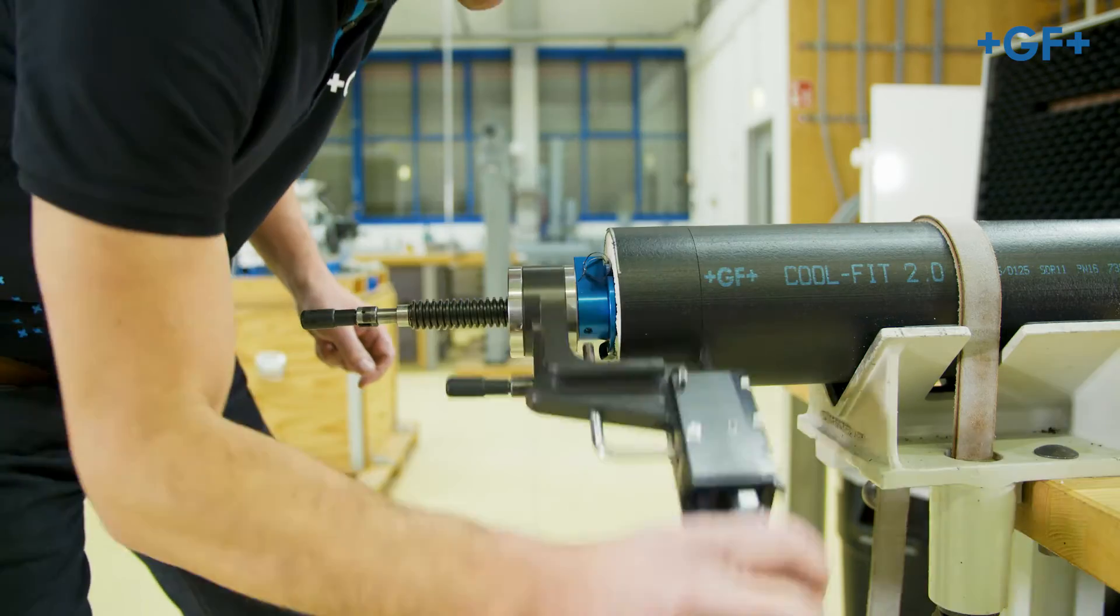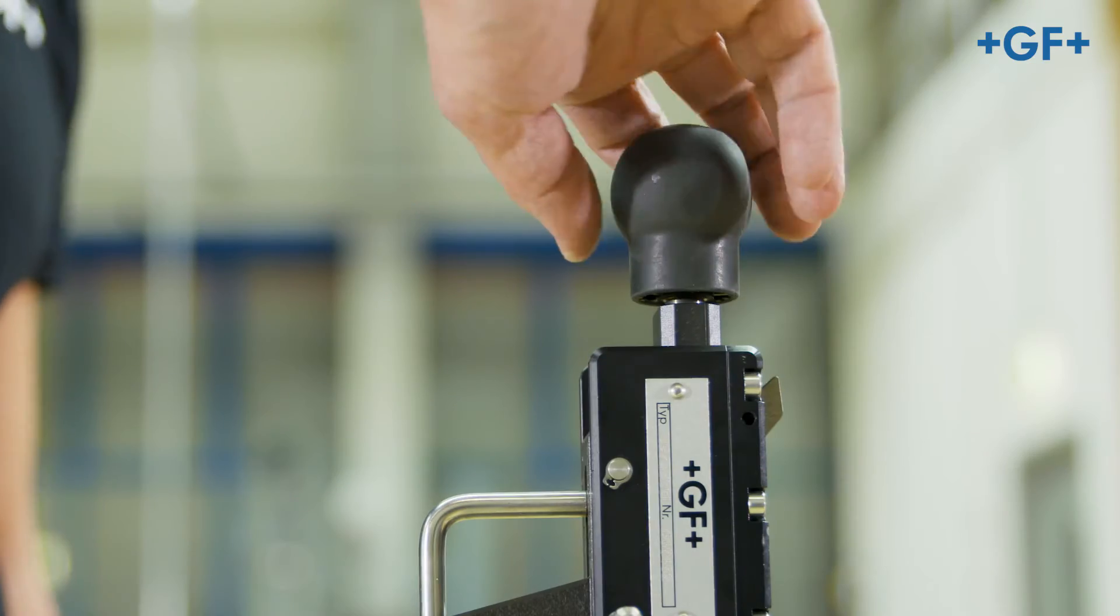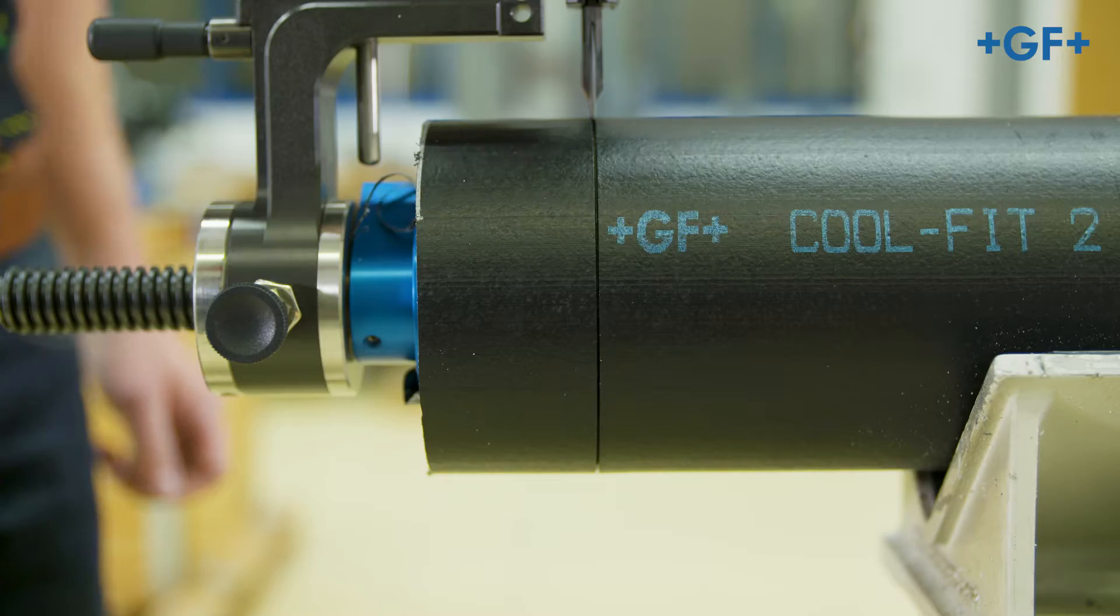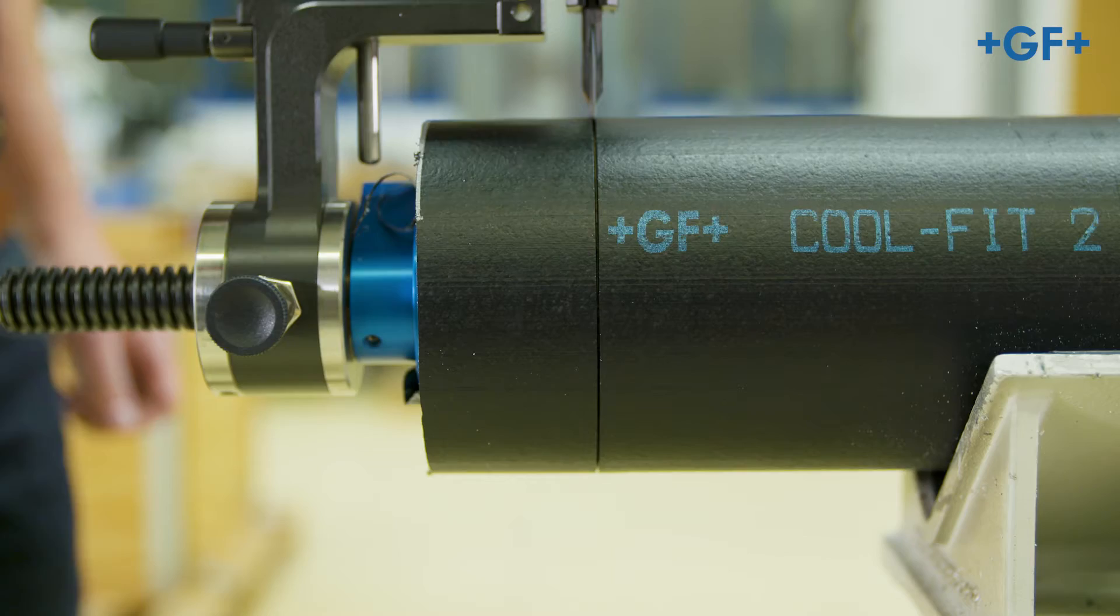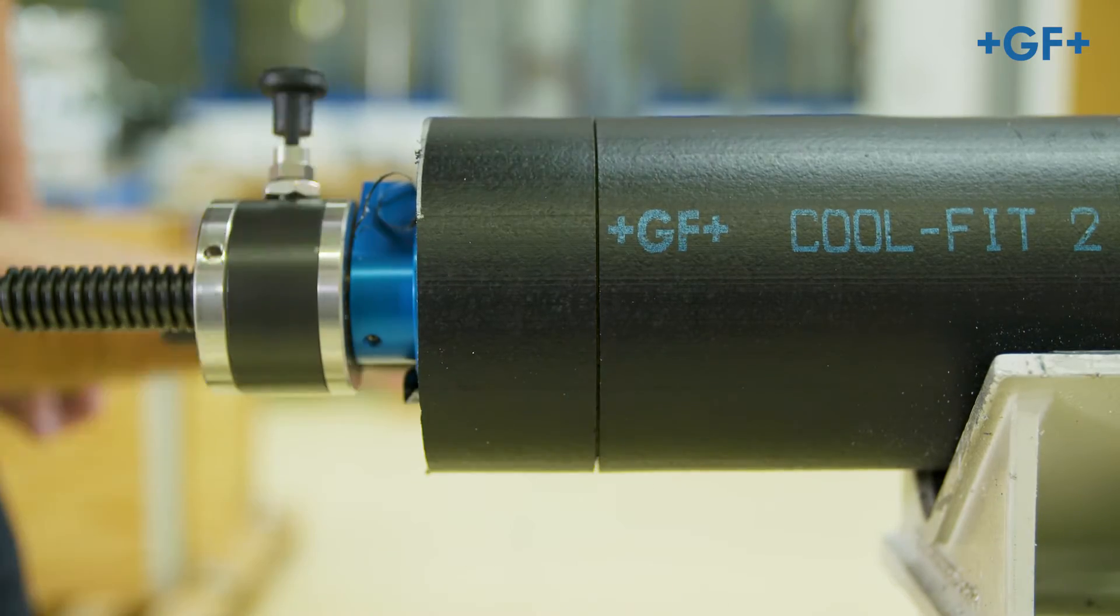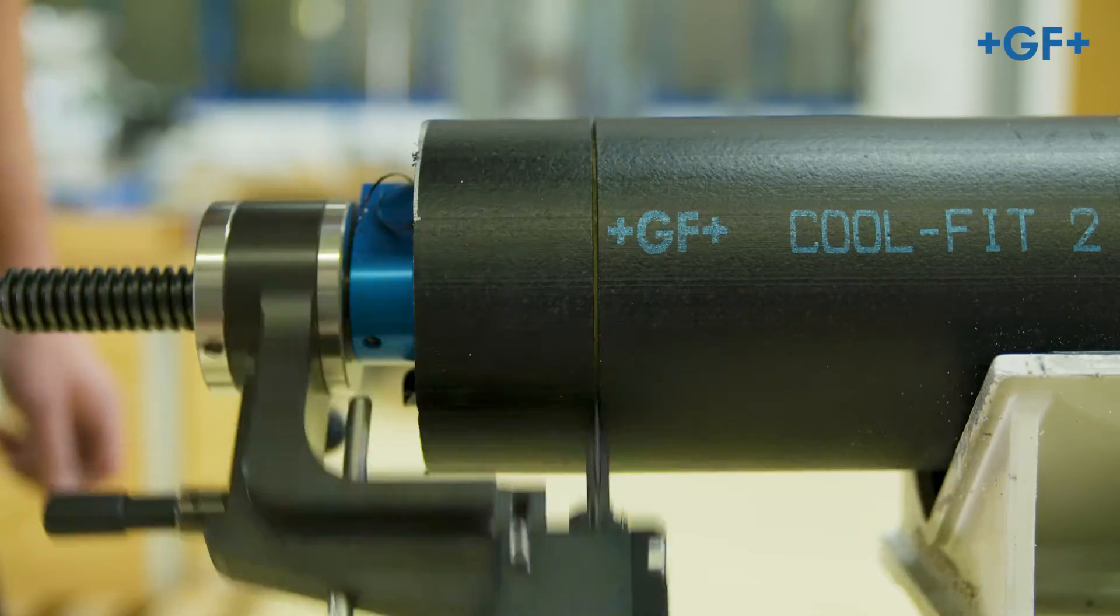Turn the foam removal unit once clockwise and move the blade forward by a quarter turn at the lever. Continue doing so until the insulation audibly separates from the CoolFit pipe.